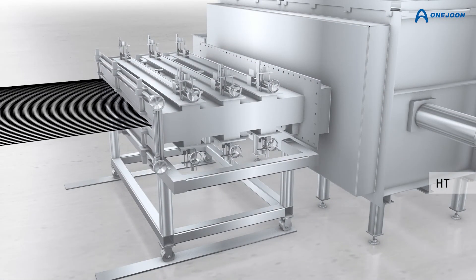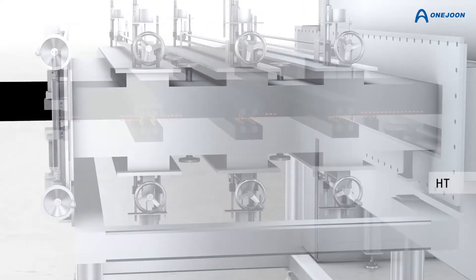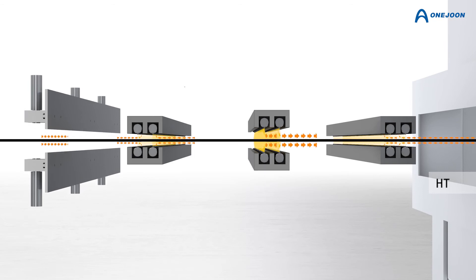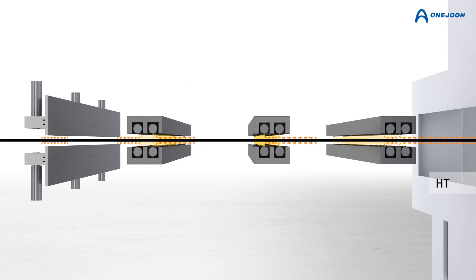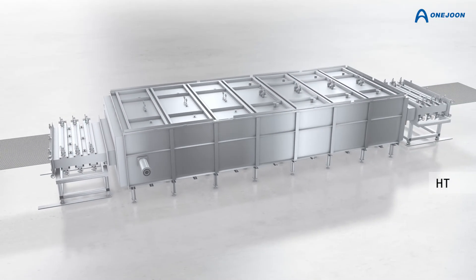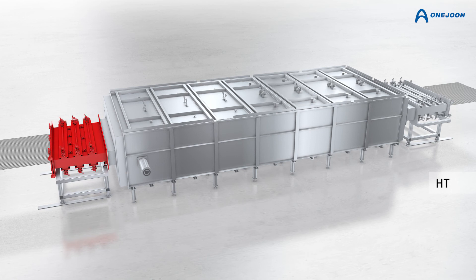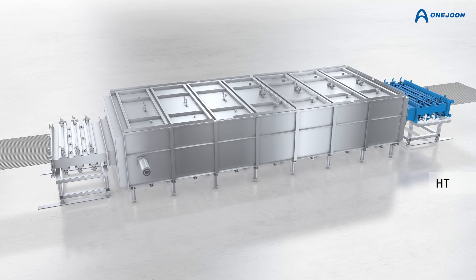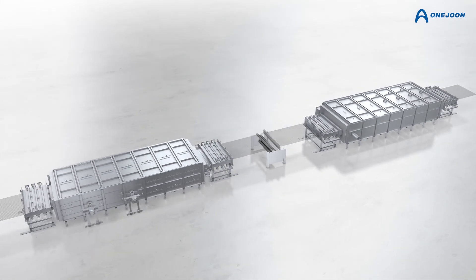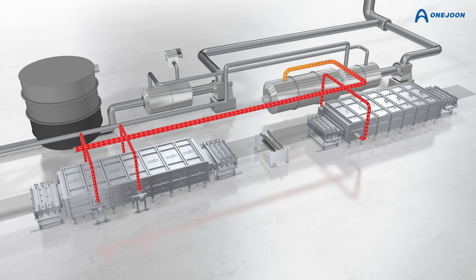The furnace ceiling boxes include individually adjustable distortion-free openings. This proprietary design guarantees minimal transition gaps and 100% sealing against ingress of atmospheric oxygen with low consumption of inert gas. Easy access to the furnaces is provided due to the modular design of the ceiling boxes. The insulated inlet ceiling boxes can operate with preheated inert gas, while the water-cooled outlet ceiling box and inert gas supply work together as a cooling zone. Exhaust gas ports can be individually placed based on process needs to ensure uniform flow of the process gases. Insulation or heat tracing of the exhaust gas ductwork to the combustion chamber prevents condensation and the buildup of tar.